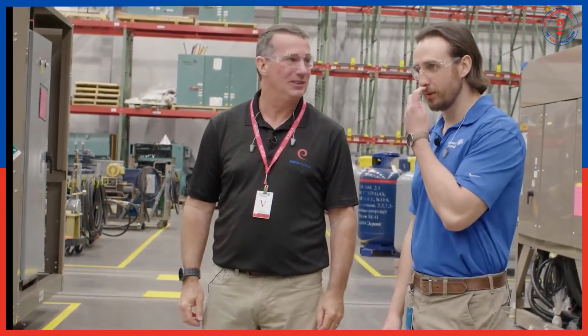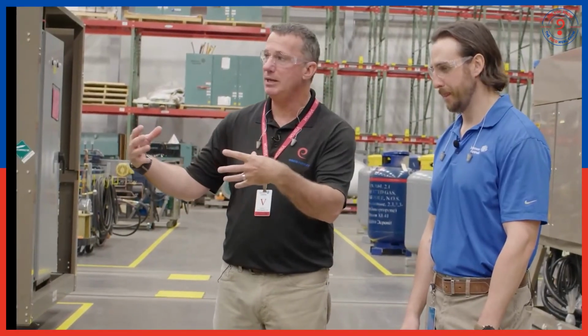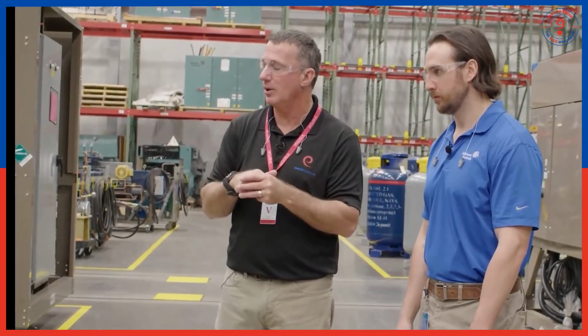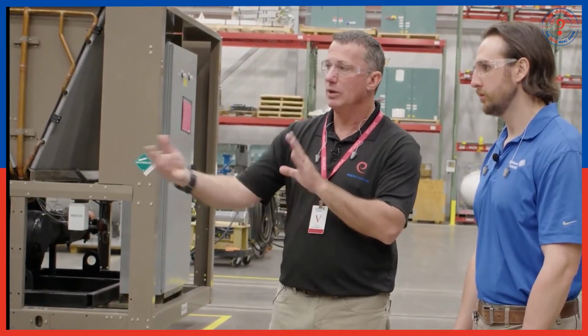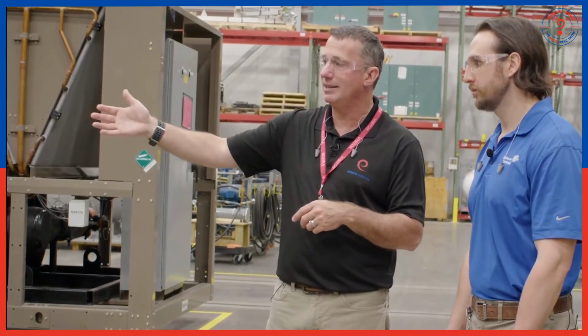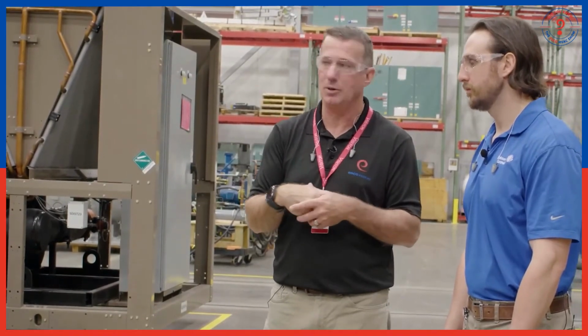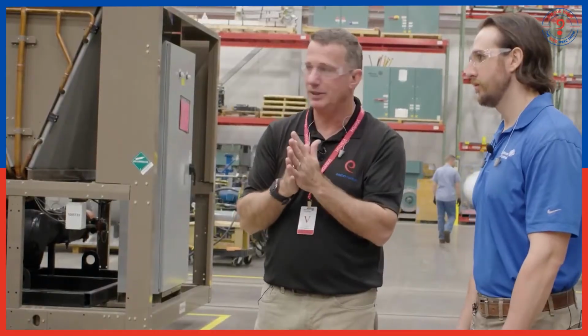It was at our San Antonio water-cooled factory, and now it's here for different purposes. So what we're actually doing is we're suspending our rotor inside of our compressor with our magnetic bearing assembly, but then we're looking for imbalances or shifts within that rotor. And so the reason that you actually have that hammer here is once someone rotates that like it was an operation, you can actually see the resonance from the impact of that hammer to be able to measure, monitor, and then of course the algorithms we're going to try to readjust to get that rotor back centered within the assembly.